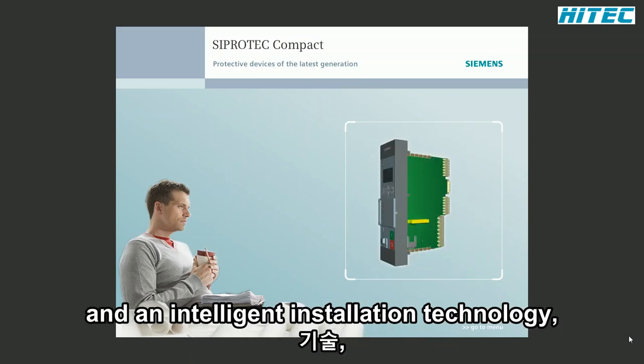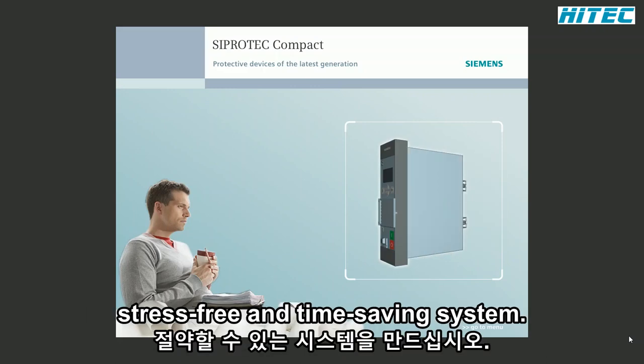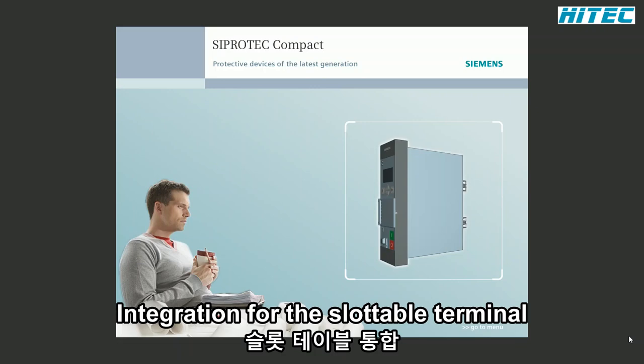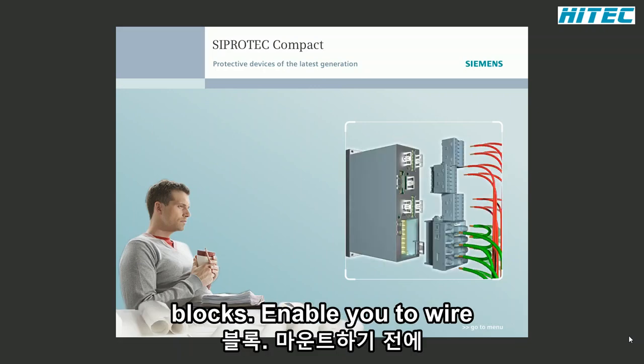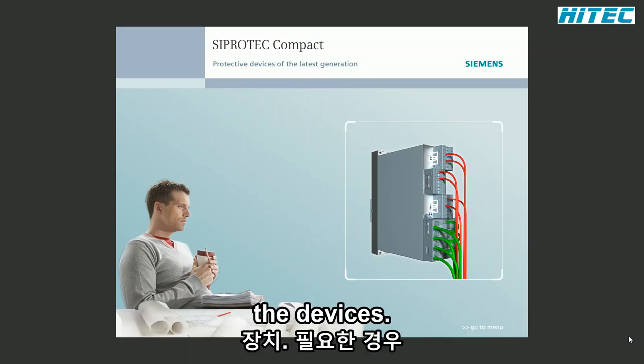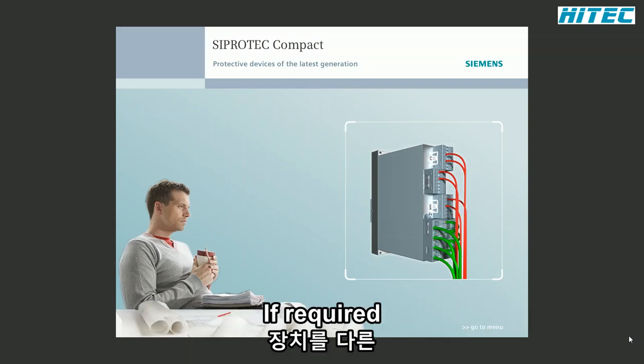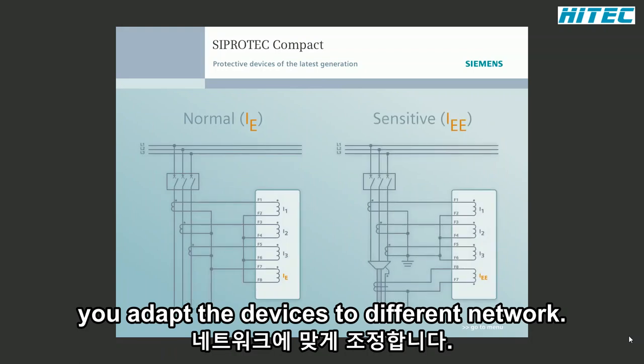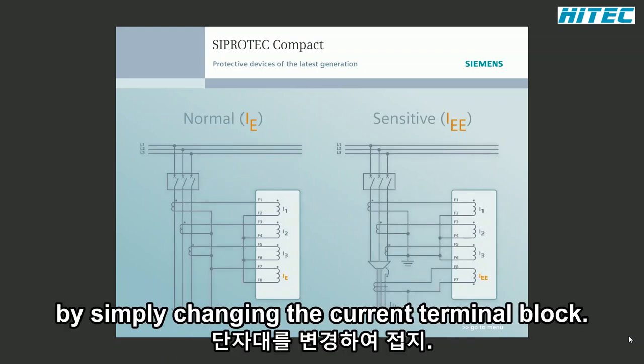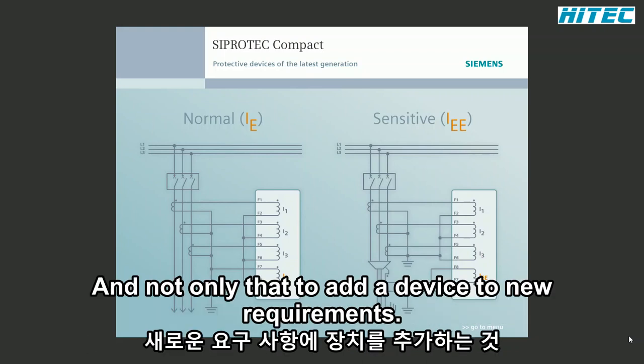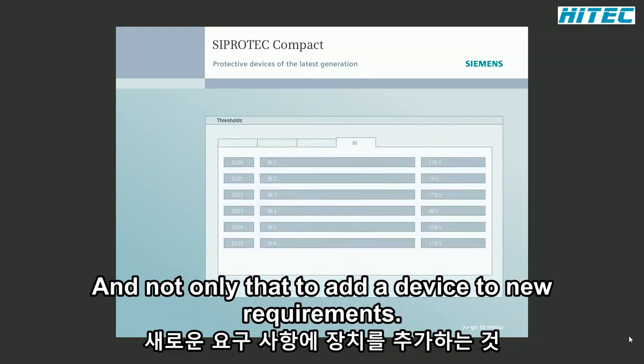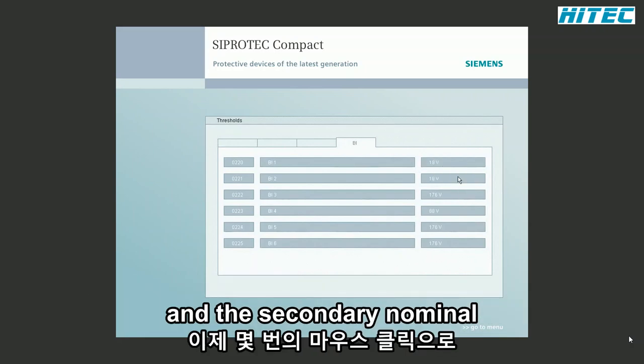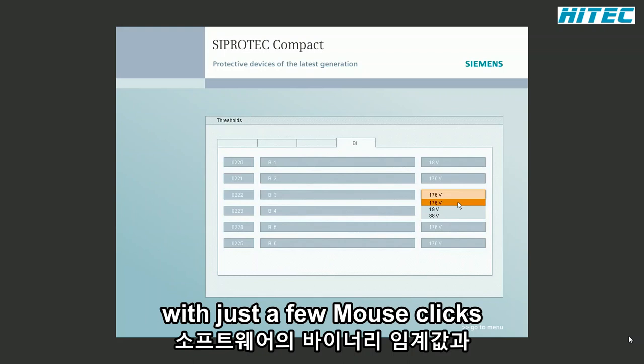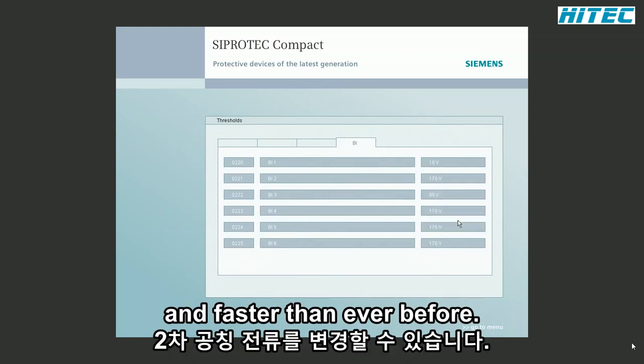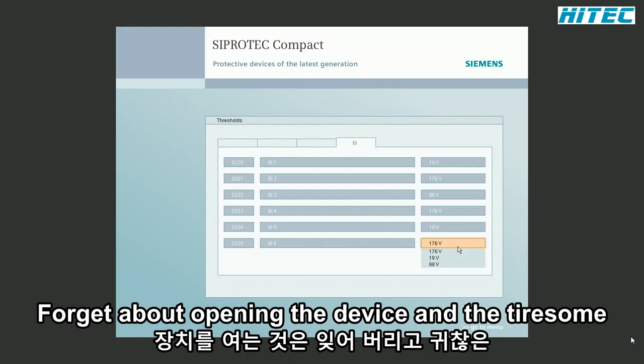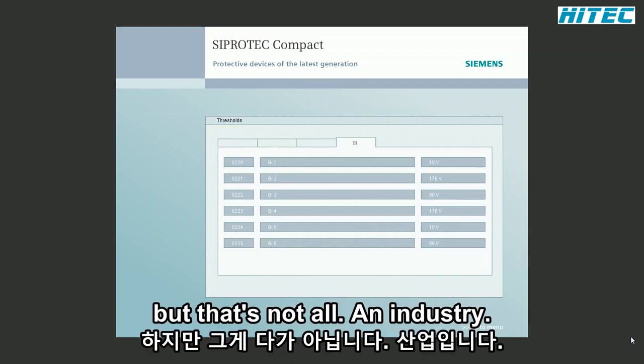The modular design and an intelligent installation technology make for stress-free and time-saving system integration. For the slottable terminal blocks enable you to wire and test the system before you mount the devices. If required, you adapt the devices to different network neutral point groundings by simply changing the current terminal block. And not only that, to adapt a device to new requirements, you now change the binary thresholds and the secondary nominal current per software, with just a few mouse clicks and faster than ever before. Forget about opening the device and the tiresome rearrangement of jumpers. But that's not all.